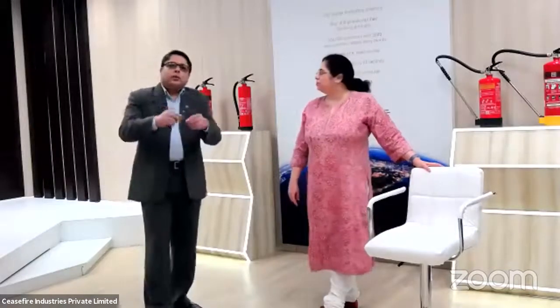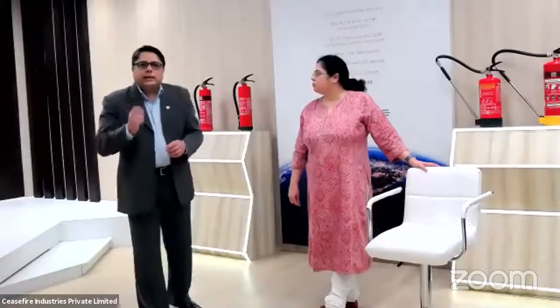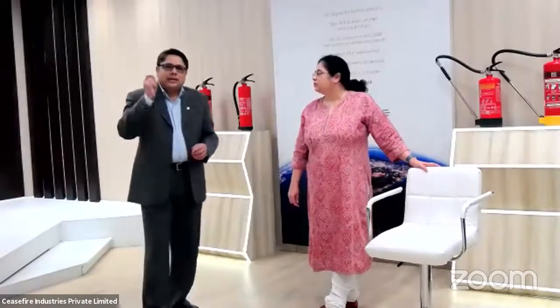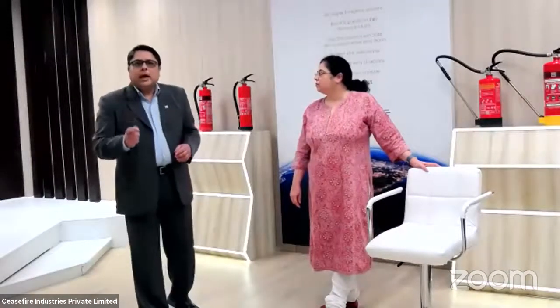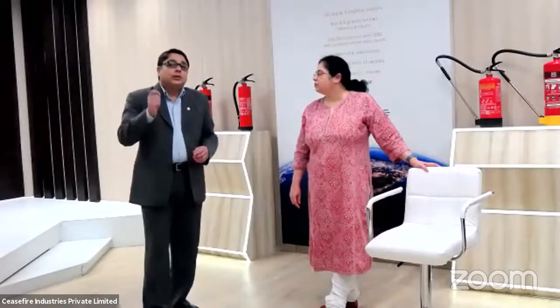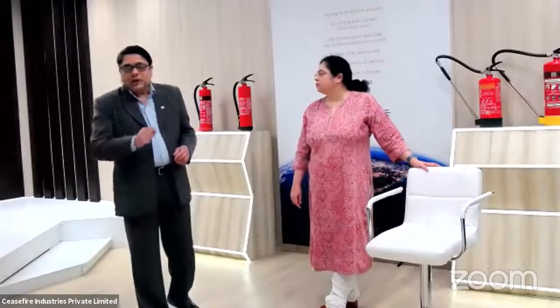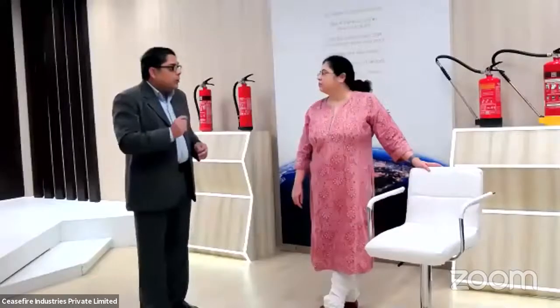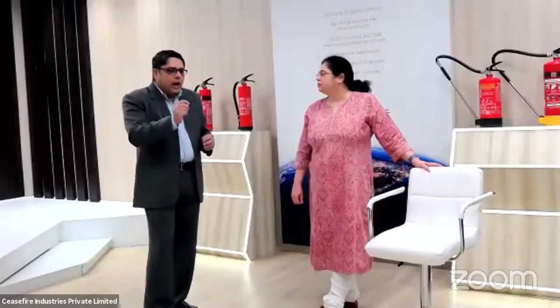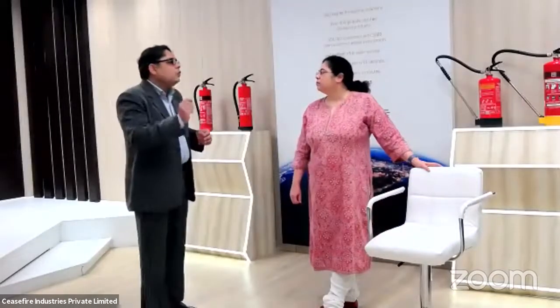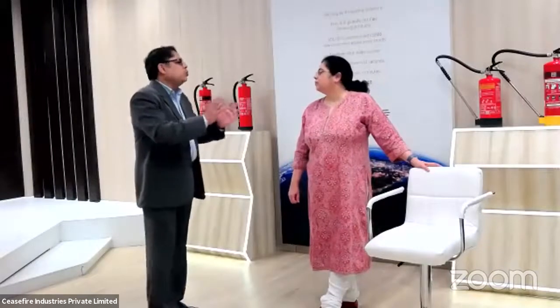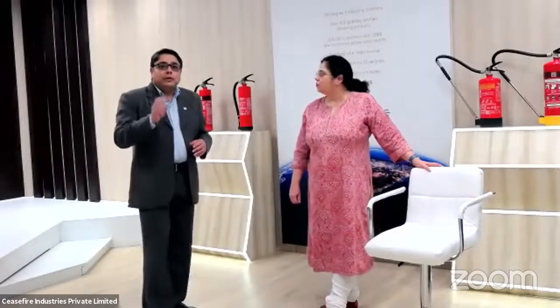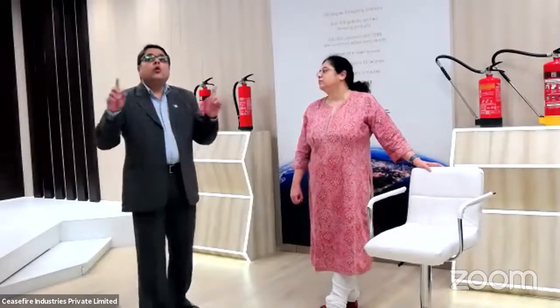So as this tube runs through all enclosures, it detects the precise area where the fire has happened. And secondly, it also delivers the extinguishing agent to that very spot. This is what is so unique about it, because if you can identify how much agent you require, it is always a very small quantity, up to 2 kg. And that means with very little extinguishant, you can protect your whole panel.